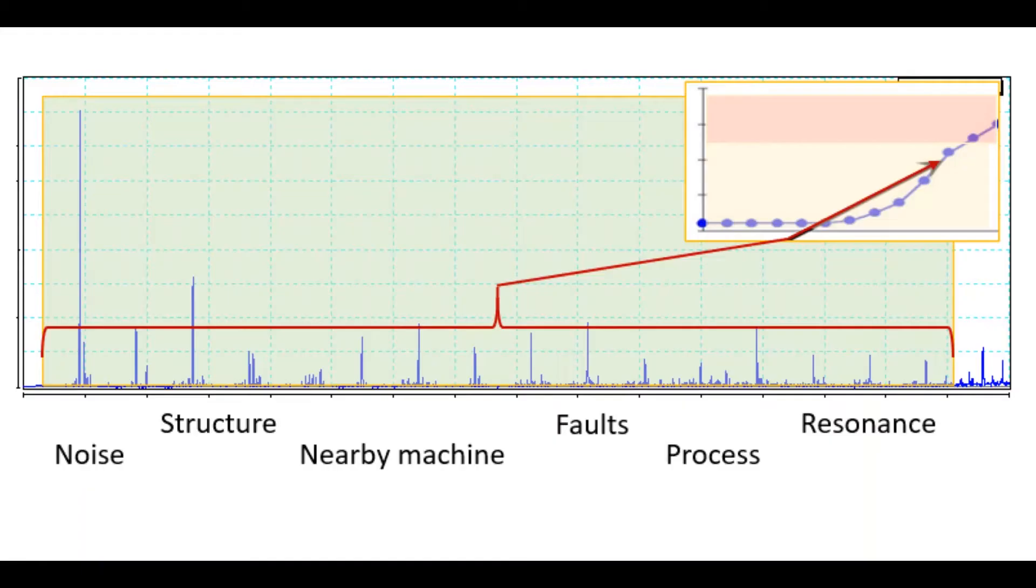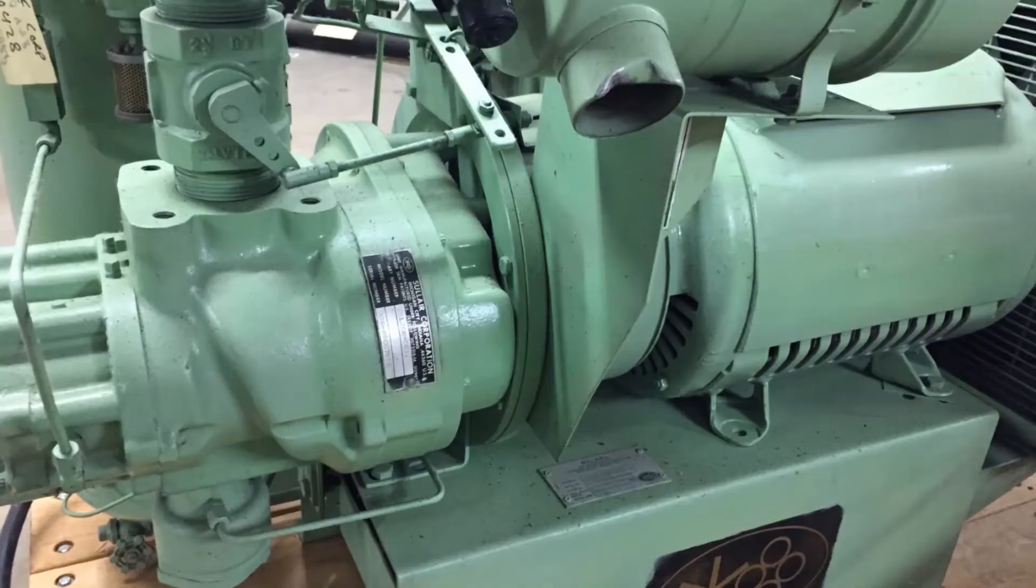The broadband alarms used in vibration screening provide a simple number which is easy to trend, but it combines all the vibration signals from all sources. It could be a fault, but it could also be something else. This means that further testing is needed.